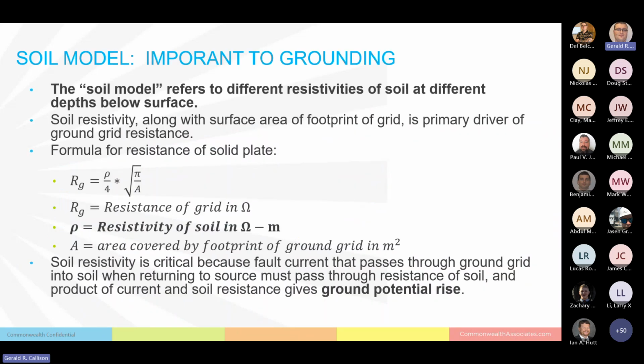So let's talk about that soil model. It's very important to grounding. The soil model just refers to different resistivities of soil at different depths below the surface. Soil resistivity, along with the surface area of the footprint of the grid, is going to be the primary driver of your grid resistance. Now, I have a formula for grid resistance.